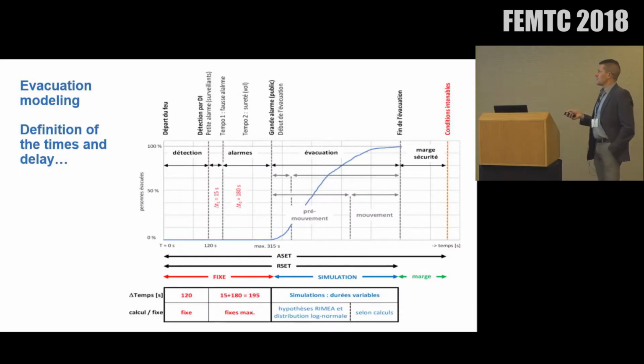One of the constraints, a very strong constraint from the client, was the willingness to stop people going out of the library with the books in case of emergency. So they had put more than 3 minutes delay between the alarm and detection and the effectiveness of the alarm. So this has complicated the evacuation possibility a lot with this project.